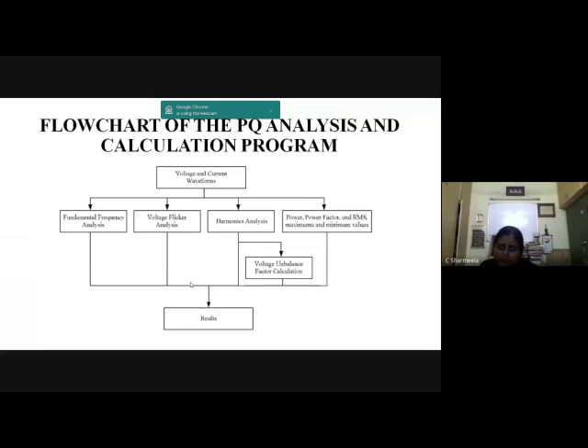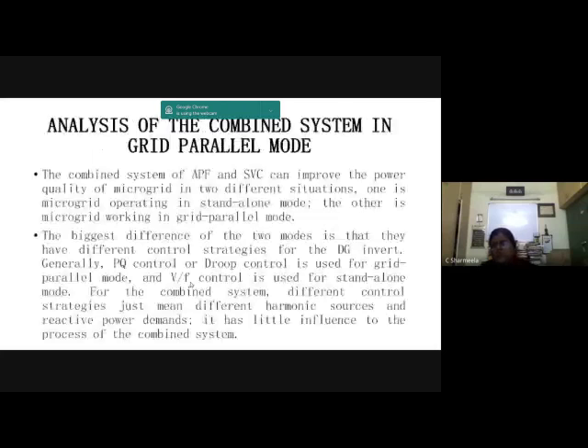So when you pass it on to that algorithm, it will try to tell whether the disturbance is flicker or harmonics, or unbalance, etc. And you can have a combined system which will give you the monitoring of the PQ. So in the case of a microgrid, you again put an active power filter at the front end, right? You have a distributed generation connected to the inverter, but these distributed generators are utilizing power electronic devices. They may inject harmonic problems into the network. So that is going to pump PQ issues into the network. You are able to see that on the system, and you can monitor them with the help of your PQ monitors.